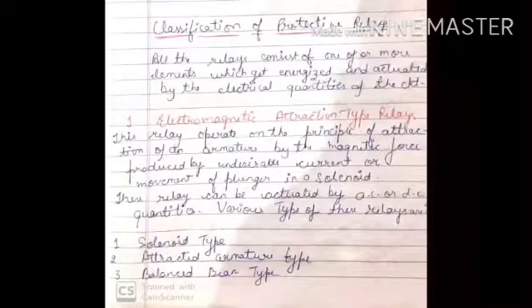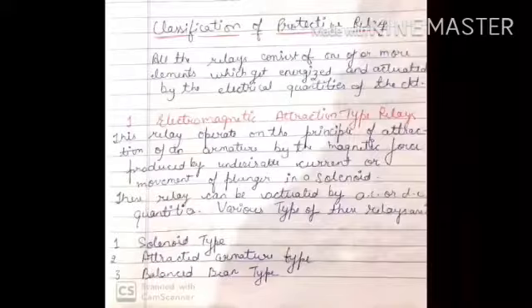The electromagnetic attraction type has three subtypes. First is the solenoid type, where the plunger or iron core moves into a solenoid and the operation of the relay depends on the movement of the plunger. Second is the attracted armature type, which operates on the current setting — when the current in the circuit exceeds beyond the limit, the armature gets attracted by the magnetic force.